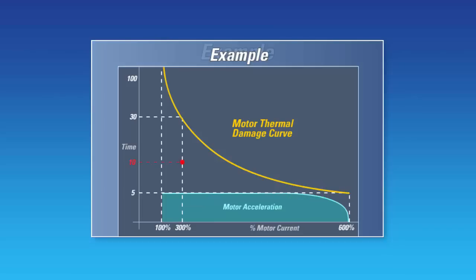The protection relay tripped 10 seconds into the start. The customer notes from the relay data that during the start, the motor drew 600% rated current for 4 seconds, and then the current dropped to 300% for only 6 seconds before the relay tripped. Given that the thermal damage curve was selected correctly, the customer wants to know why the relay tripped the motor even though the current draw did not exceed the thermal damage curve limits. The answer is quite simple and clearly explains motor thermal modeling.